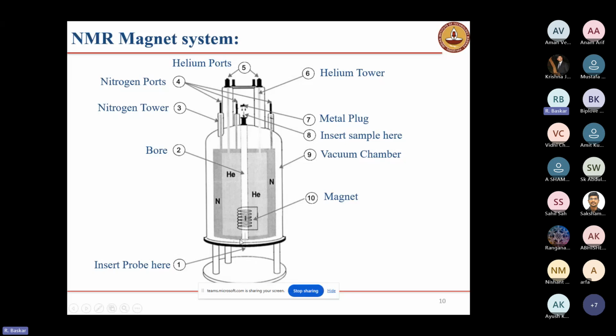Here only we are inserting the probe. This is the superconducting coil, and this is the helium, and the next one is the liquid nitrogen. These are the vacuum chambers. Here we insert the sample. Once we insert the sample, with the airflow it will float and reach the probe. Here we have connected the probe.